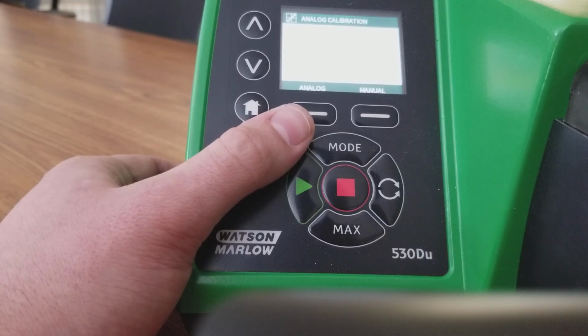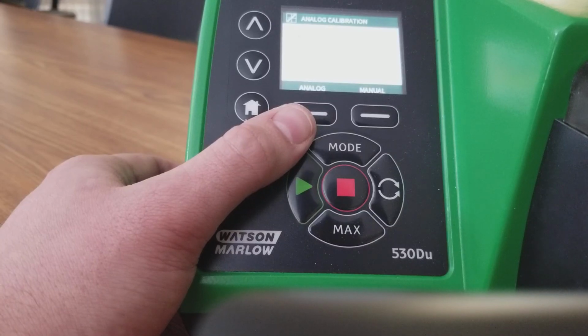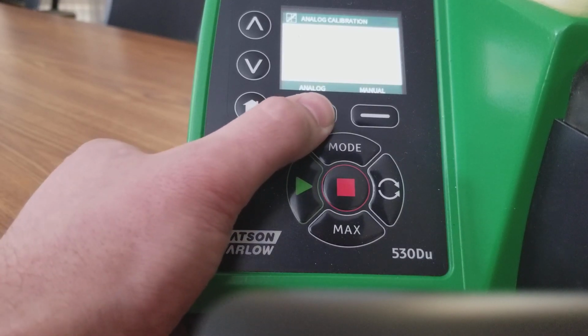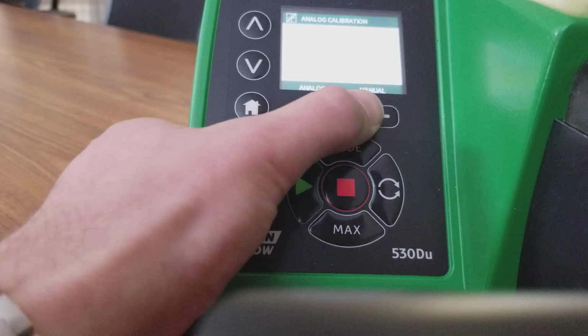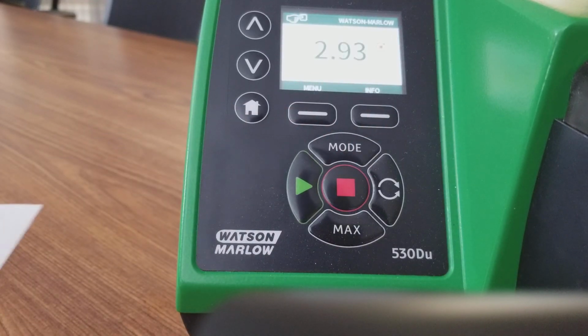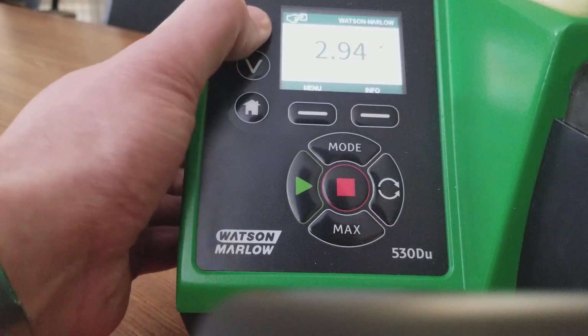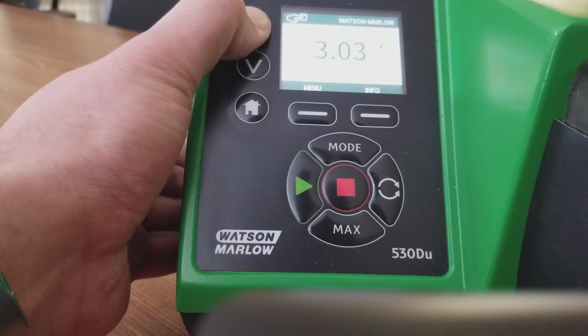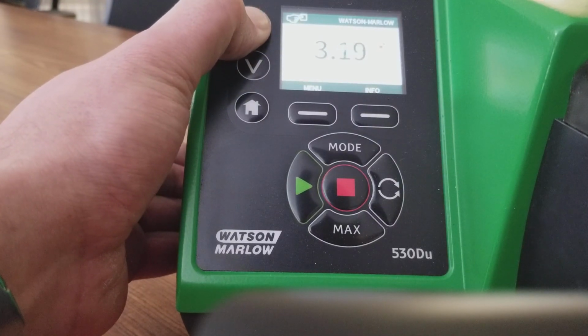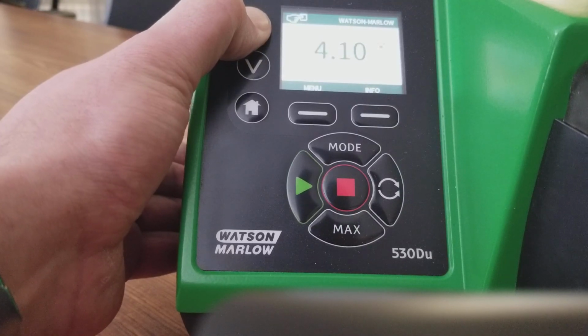At this time, if you had the wires and everything hooked up, you could go ahead and hit analog. But we'll go into manual and go through how the settings would end up being if we were to set it up slightly differently. Let's say that you weren't using the full range of the pump and you were going to limit it to, say, 5 gallons per hour, for instance. So we would hit the up arrow in the manual mode and select 5 gallons per hour.